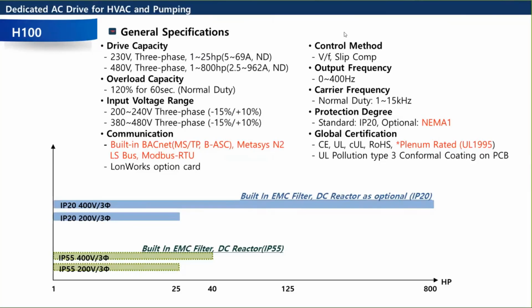It's a V/F drive, so that's volts per frequency. We also have slip compensation, which may be useful for compressors where you need to get some higher starting torque. Carrier frequency ranges from 1 to 15K. These are all IP20 drives, just like all of our other drives. And then you can get NEMA 1 kits or conduit kits that give you the NEMA 1 rating as an option. All the standard certifications are okay: UL, CUL, CE, and RoHS. The plenum rating is something that's nice. You could actually mount the drive in a plenum, which some of the HVAC guys care about. And then we have the conformal coating type 3 on all of our printed circuit boards.